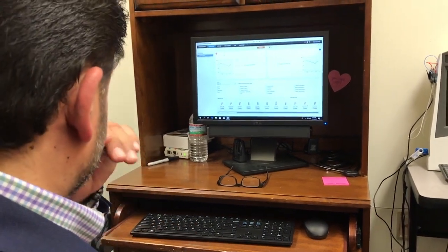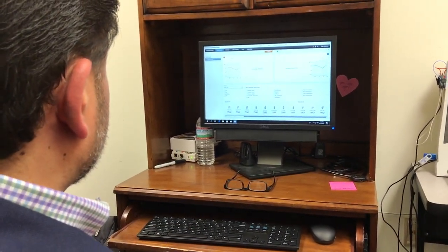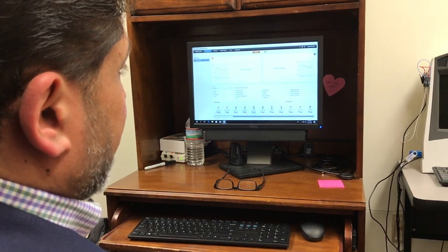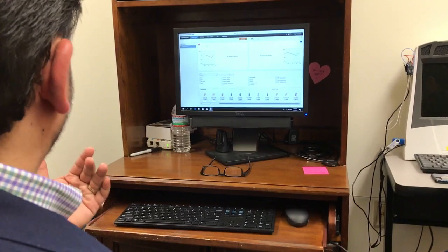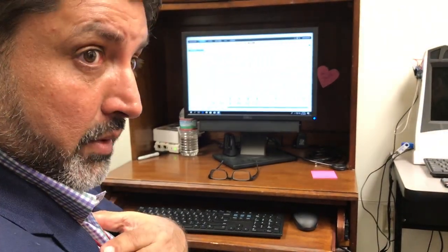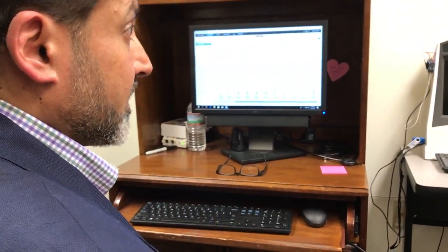To guess, you're going to get about 5 dB more gain with an ITE mic than you are with a BTE. So I'm going to go with an IT here. That's how I'm thinking this through. You're trying to do as much natural gain as possible.